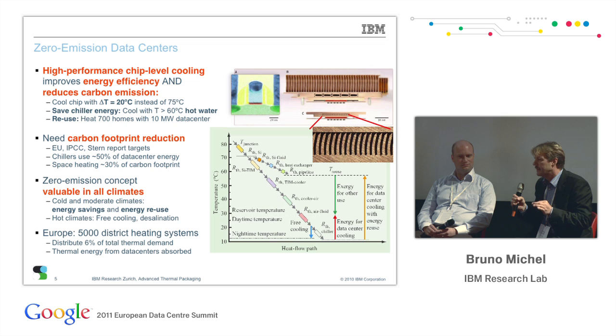With that approach, we can reduce the energy consumption to a considerable fraction, depending on the temperature outside, and we can heat houses. We can heat 700 homes, typical family homes, from a 10 megawatt data center. That's peak load. It would be more if it's band load. And there is a lot of distribution systems available in Europe that can distribute the heat. 6% of thermal demand of Europe is being transported with a district heating system, and the thermal demand in Europe is 30% of the carbon footprint. Data centers are 2%, so we have a 15 times larger market to sell to. So we want to change.